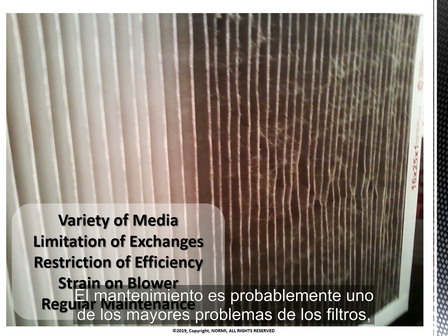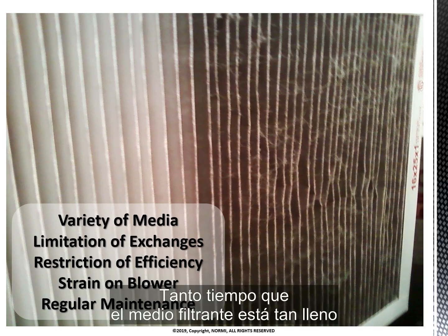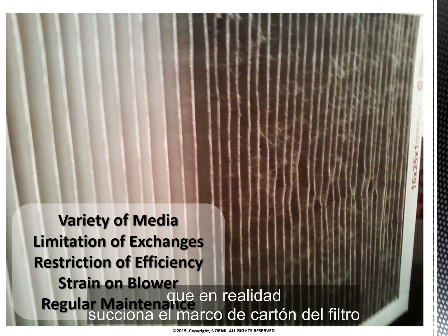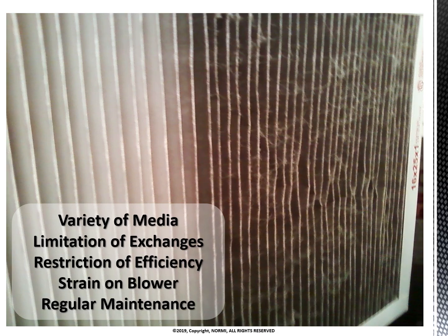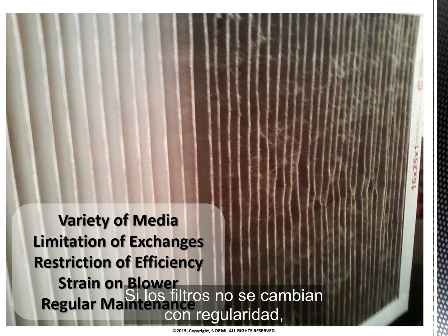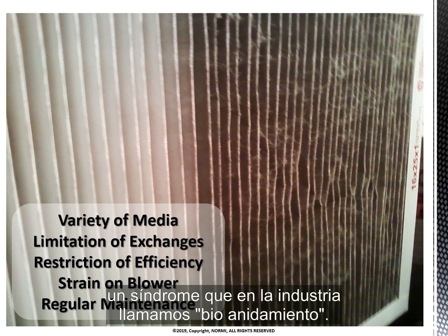Maintenance is probably one of the biggest issues with filters because people often will leave their filters in for a very long time. So long that the media is so full that it actually sucks the cardboard frame of the filter away from the edges of the return, causing blow-by. And again, the air is not filtered. If filters are not changed regularly, they can become a media for mold and bacterial growth, a syndrome that we in the industry call bionesting.